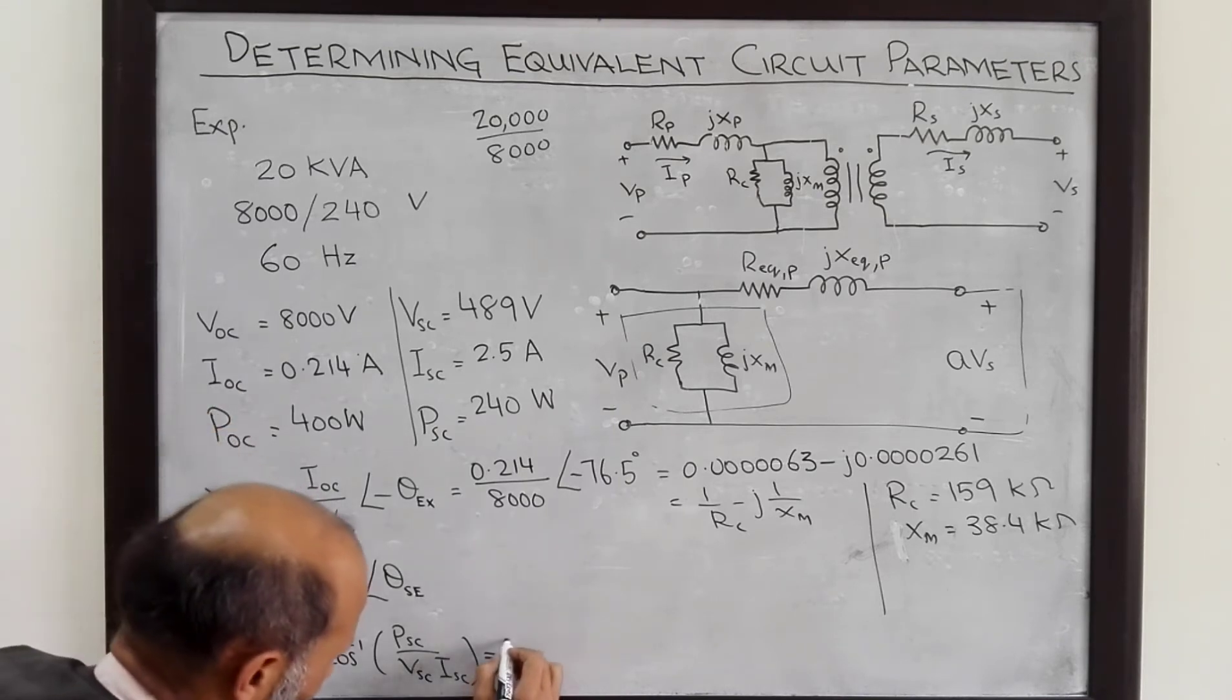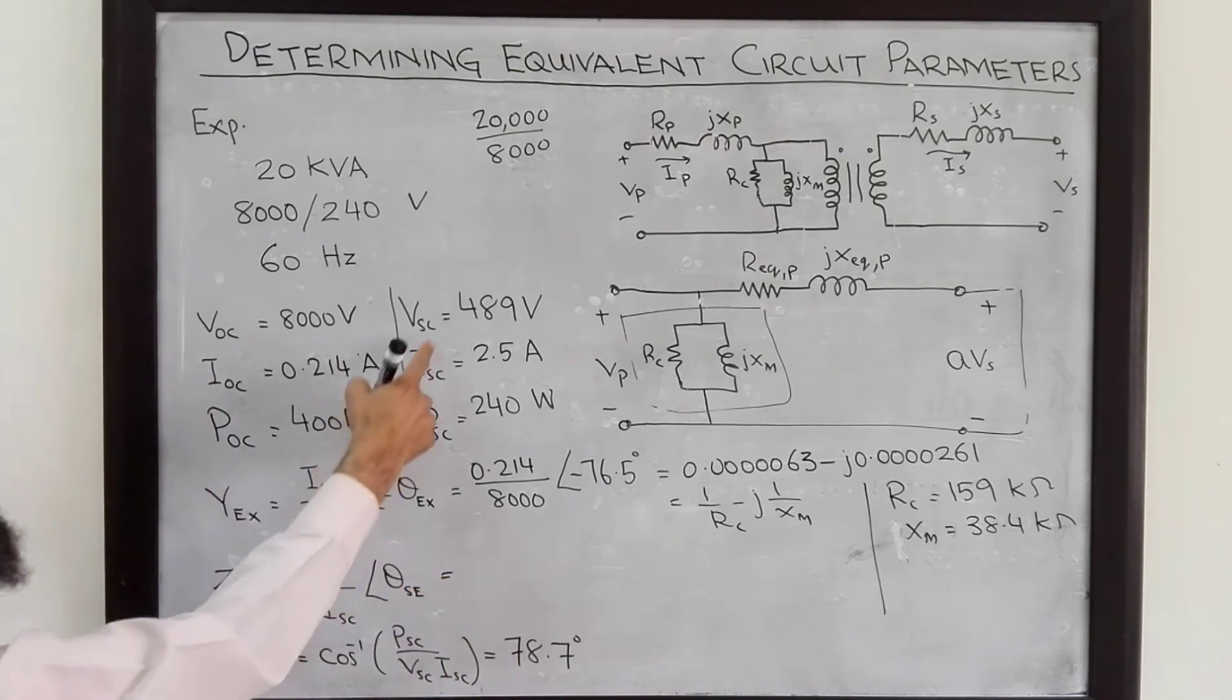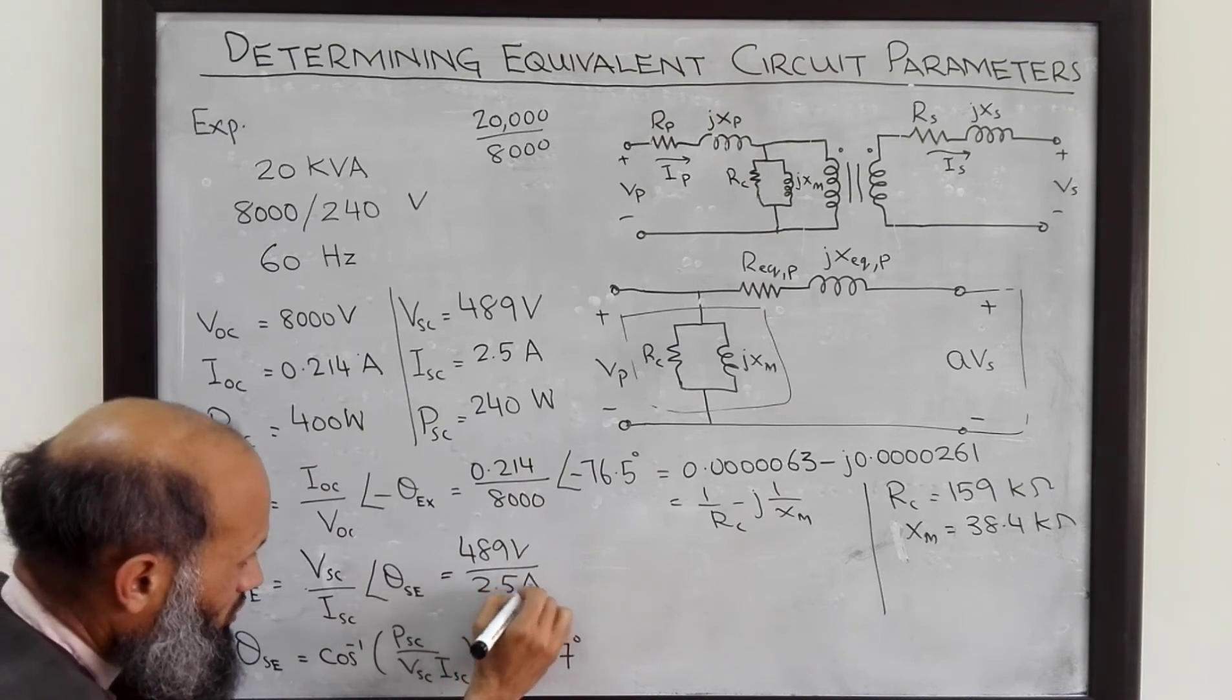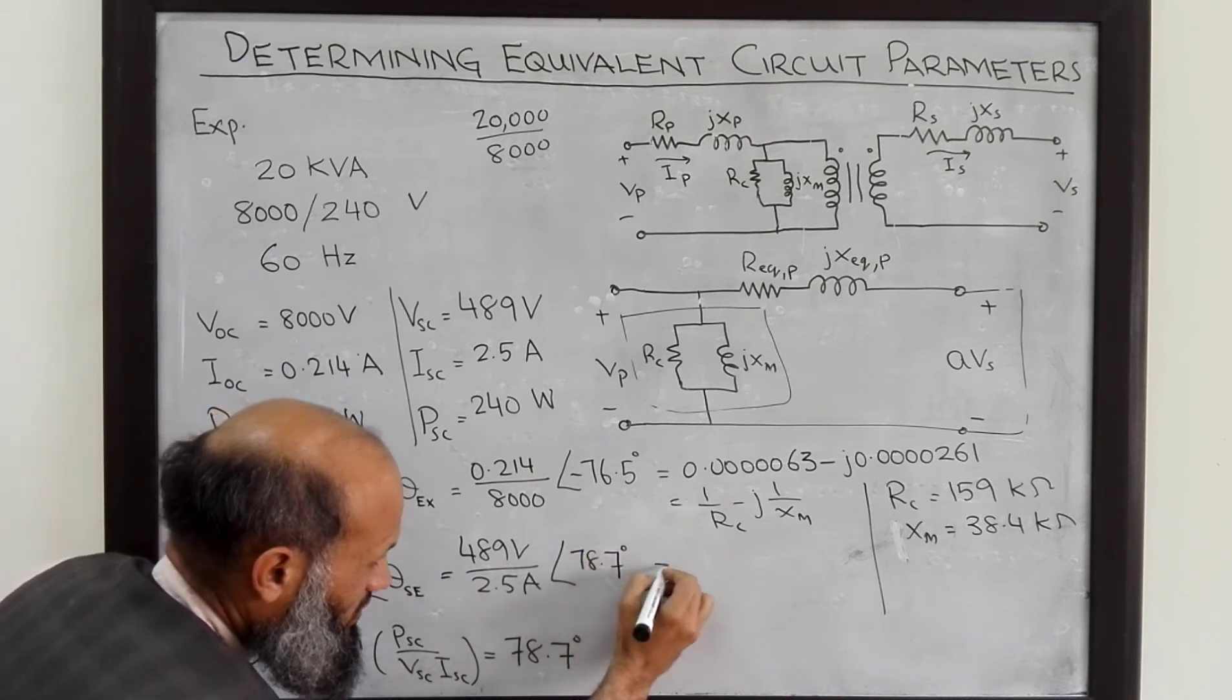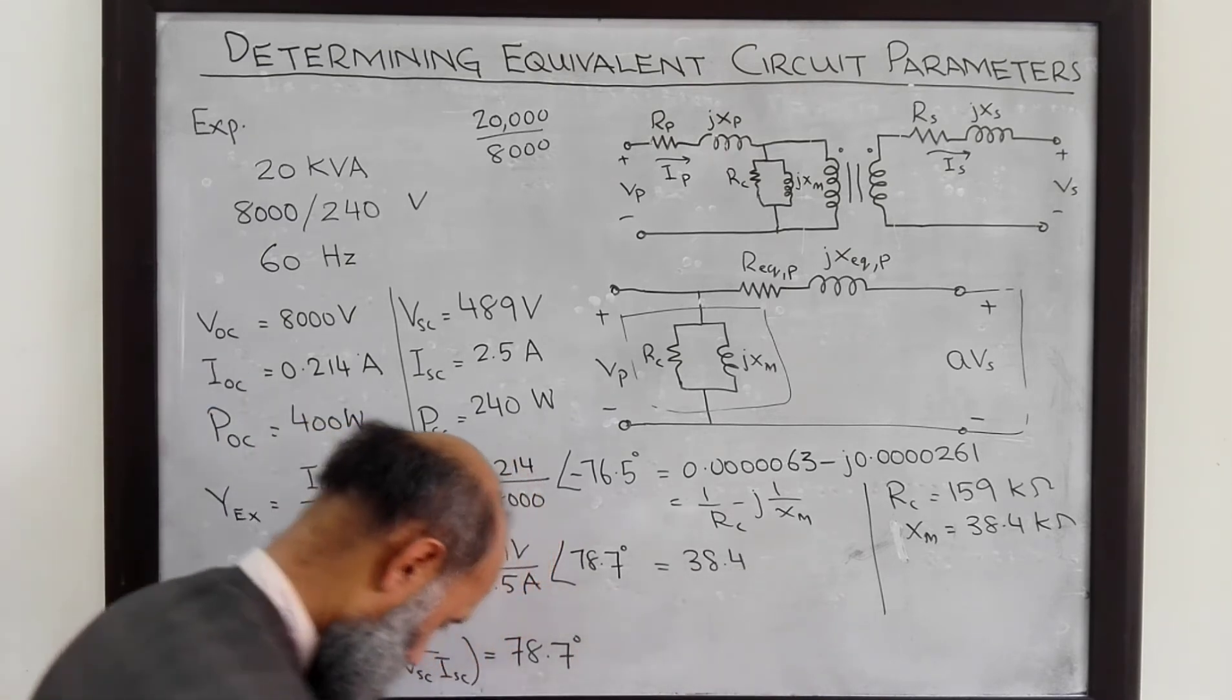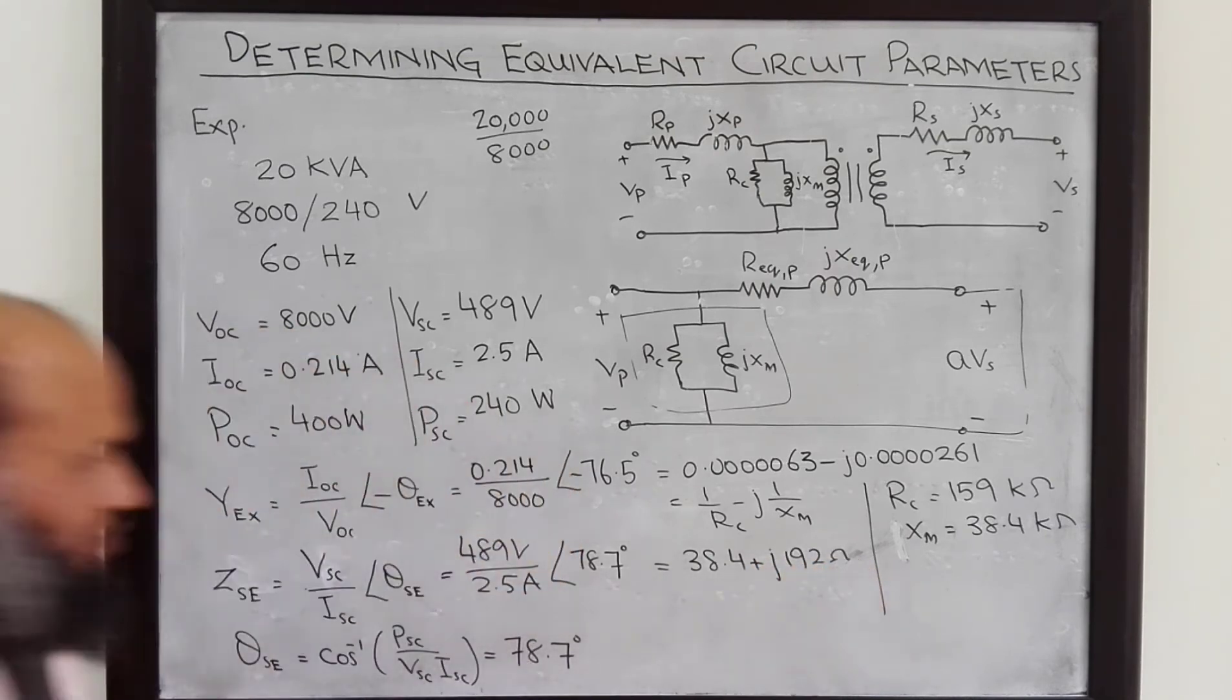And hence this series impedance, V short circuit 489 volts divided by I short circuit 2.5 amperes and an angle of 78.7 degrees. Writing this complex number in rectangular form we have 38.4 plus j192 ohms.